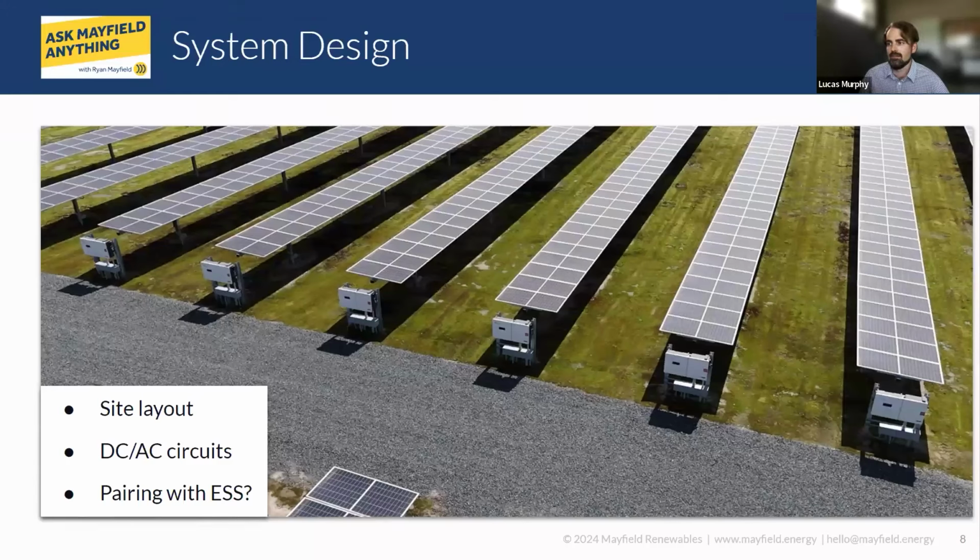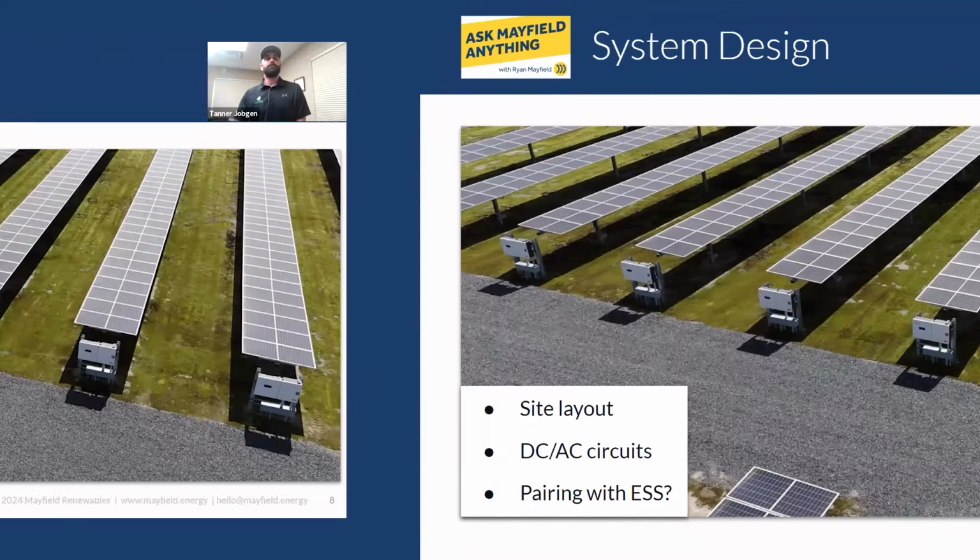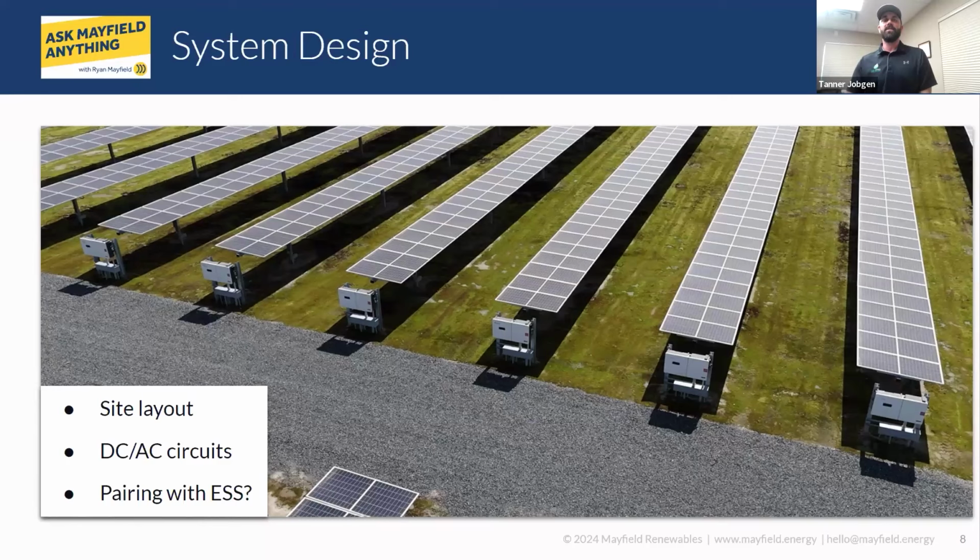The DC losses are not linear to your production, as AC losses are definitely linear. As you lose AC power, you lose production. So for that reason, most sites, we've moved to virtual central design, clustering them at the pad. With the distances, the other thing we keep in mind is the difference between running three-phase AC and DC PV. In addition to having the higher voltage, you also have less conductors. So that adds up to why it typically makes sense to try to run those on DC.